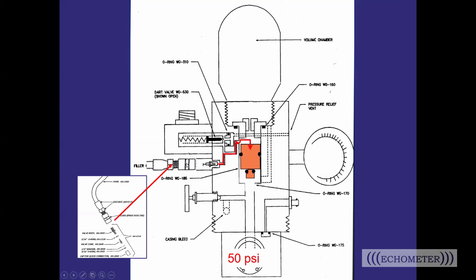All right, so we're going to pressure up the gun. That first little bit of pressure is going to follow this path, and you'll see that it comes right on top of the gas valve here. To get to the gas valve, you'd have to remove the volume chamber, remove the orifice housing, all the way down to get to the gas valve.